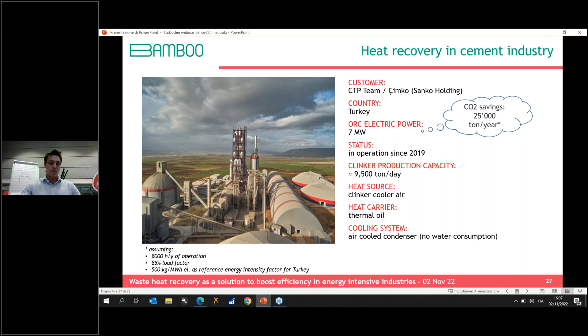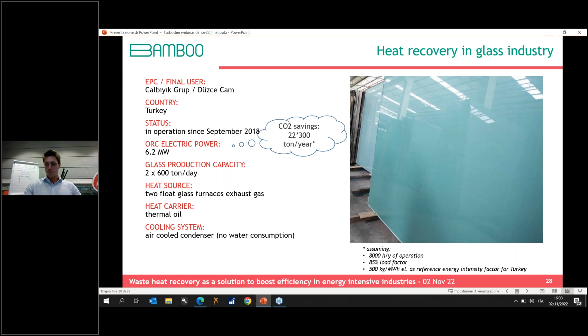This one is in the glass industry for Düzce Cam. This plant is also in Turkey, and as I was mentioning before, it is a particular size of an ORC for a glass plant because it was designed for two production lines of 600 tons per day of flat glass. And nowadays, since it has been a bit oversized, they are planning to install a third line of additional 600 tons per day of glass. And so they will saturate the potentiality of the ORC, producing up to 7 megawatt gross of power output. As I was mentioning, typically the size of the ORC in glass application is below 2 megawatt, generally from 700 up to 1200 kilowatt of gross power output.